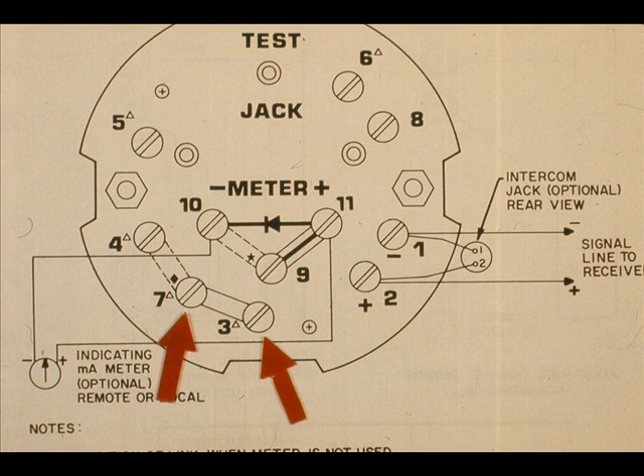The lower link is normally connected from 3 to 7 as shown. It is connected from 7 to 4 if a reverse output is desired. This link is not used with a 5-wire sensor such as is used in a rotary motion transducer.